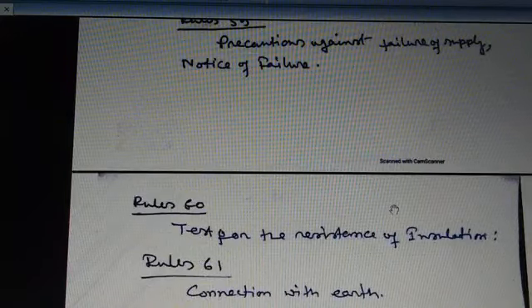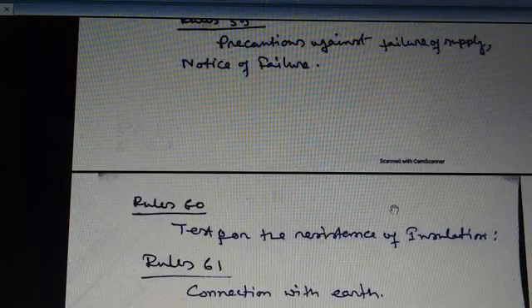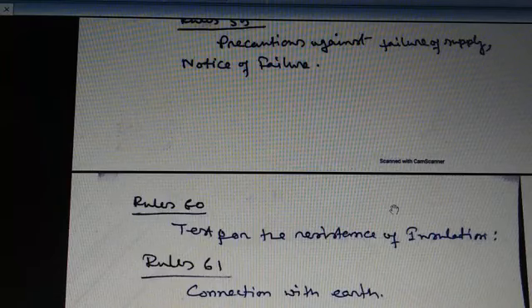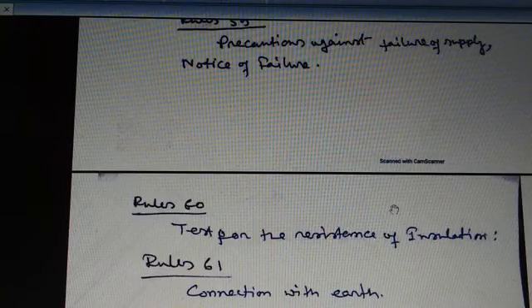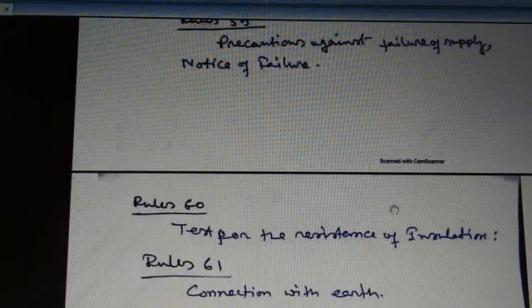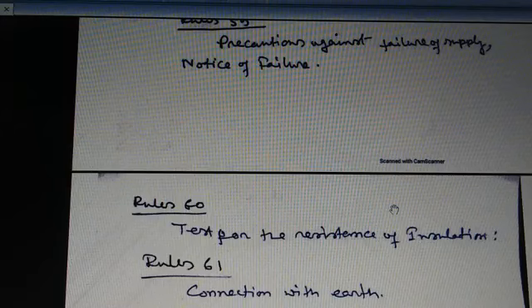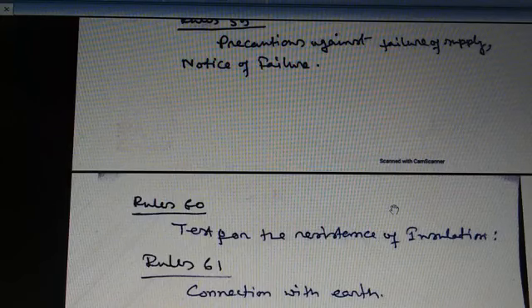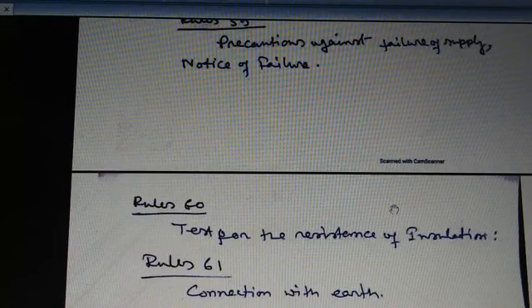testing for insulation resistance. Rule number 60 is related to insulation resistance testing. The insulation resistance testing is done by an instrument which is called the Megger. So Megger is an electrical instrument which indicates and measures the insulation resistance. The name Megger comes from the megohm, because Megger has two parts. One is the hand driven DC generator and one is the megohm meter, and the scale of the Megger is starting from infinity to 0.